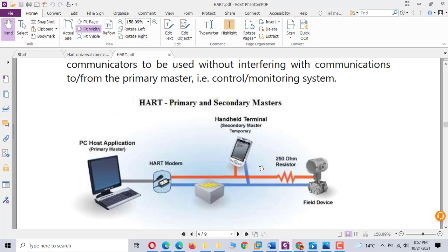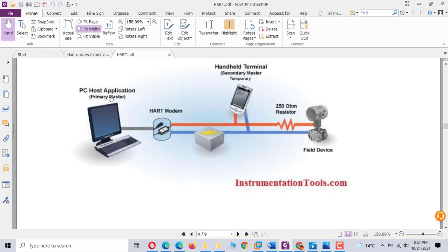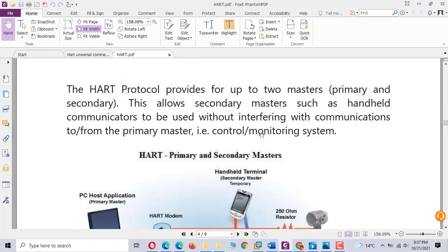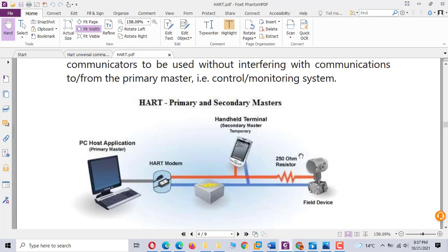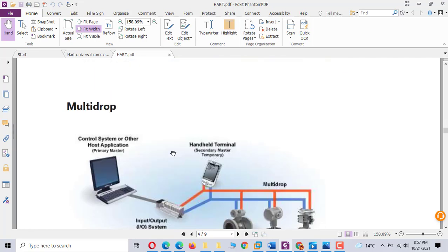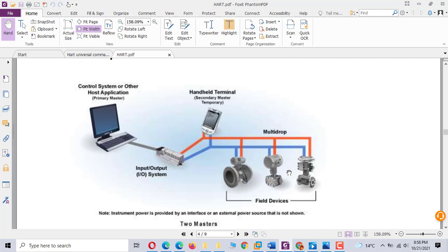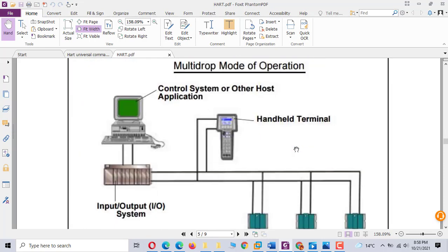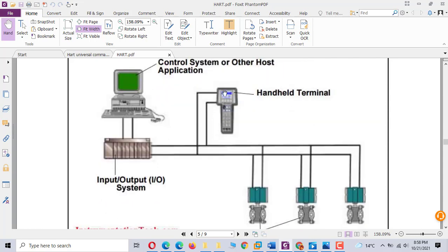This one is the PC host application. With this HART modem, every time you use HART communication, you should have a 250 ohm resistor in the loop. It is multi-drop, so you can use many HART field devices. Here is a handheld terminal, the master. This is the HART communicator, called a hand terminal. We can do everything. You can hook up here, you can hook up here, anytime. You can hook up to the DCS, the same thing.